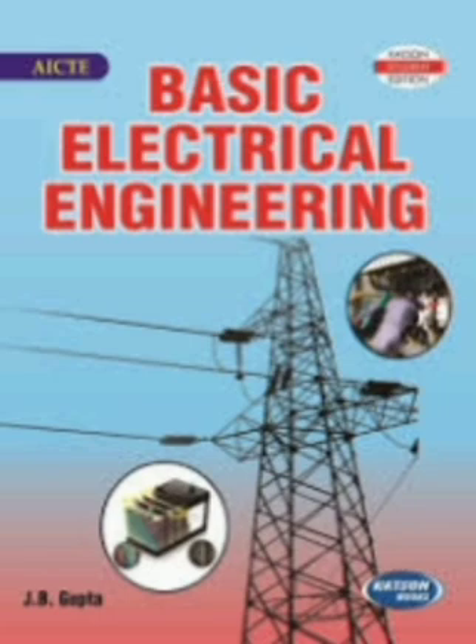Open circuit test, OC test. Main objectives of this test are to find out parameters of no load branch, that is R0 and XM of the equivalent circuit. Shunt branch parameters are used to find out constant losses in the transformer, that is core loss. This test must be conducted at rated flux condition, that is at rated voltage and rated frequency. This test is performed on LV side while HV side is open circuited.